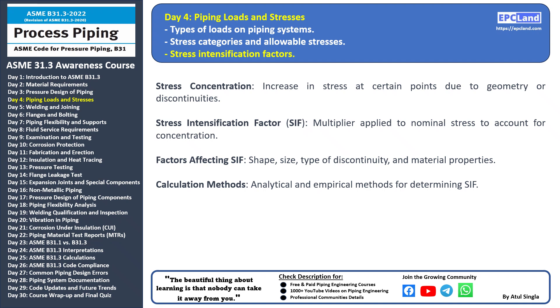The stress intensification factor (SIF) is a multiplier used to account for stress concentration. It is applied to the nominal stress to determine the actual stress at the point of concentration. The SIF depends on factors like the shape, size, type of discontinuity, and material properties. A sharp change in geometry or a sudden alteration in pipe size can lead to a higher SIF.